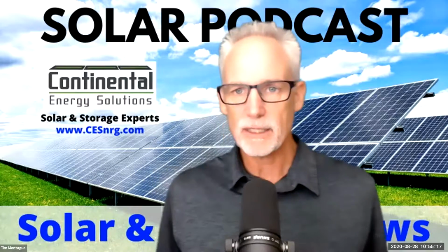So DC coupled storage works really well for an existing solar array or a new construction of a solar array. But as I mentioned earlier, if you're doing a college campus, a military base, a corporate campus, or some sort of microgrid in a community where I want batteries in separate places, as opposed to where the inverters are, AC coupling is a great solution. And that's because you have to avoid the line losses. Yeah, exactly. And it gets expensive to run long DC wires all over the place.